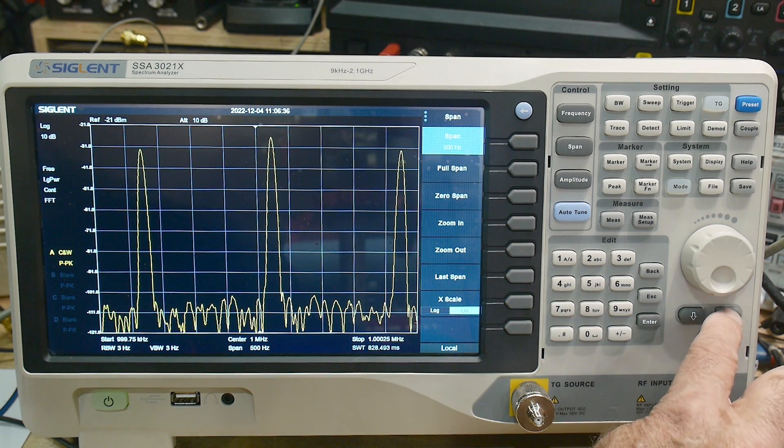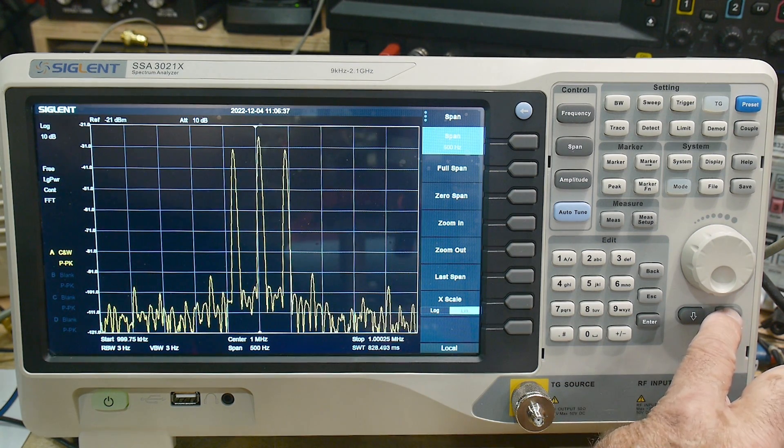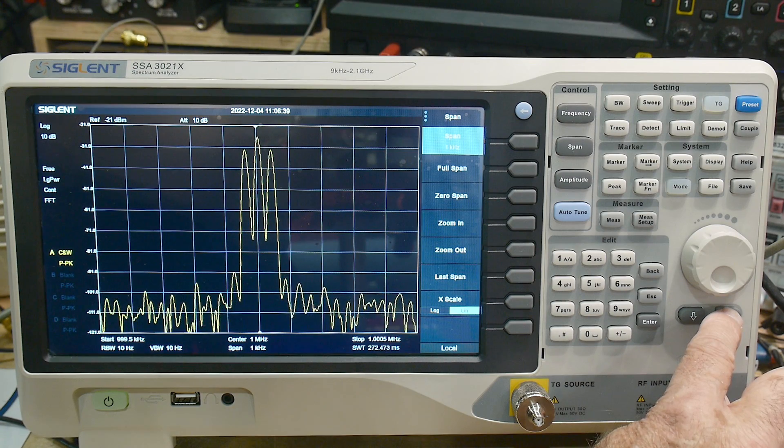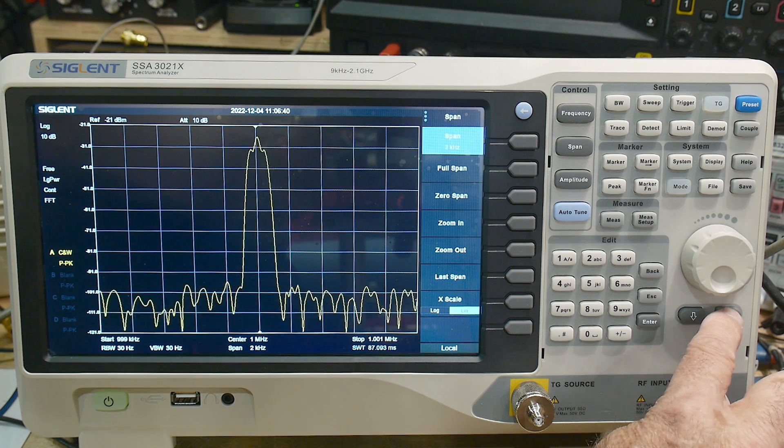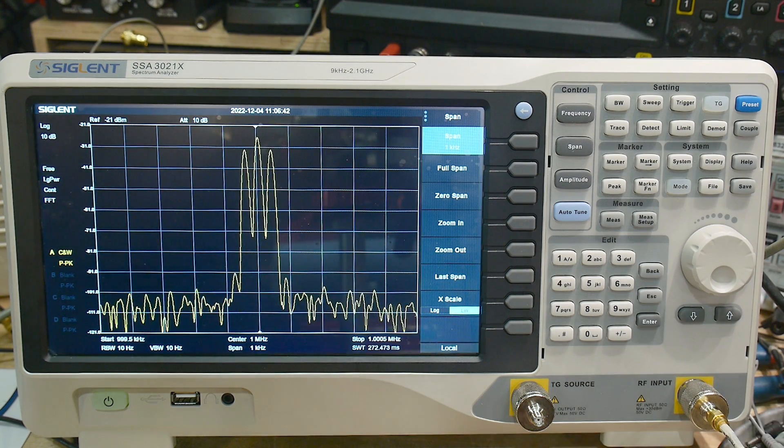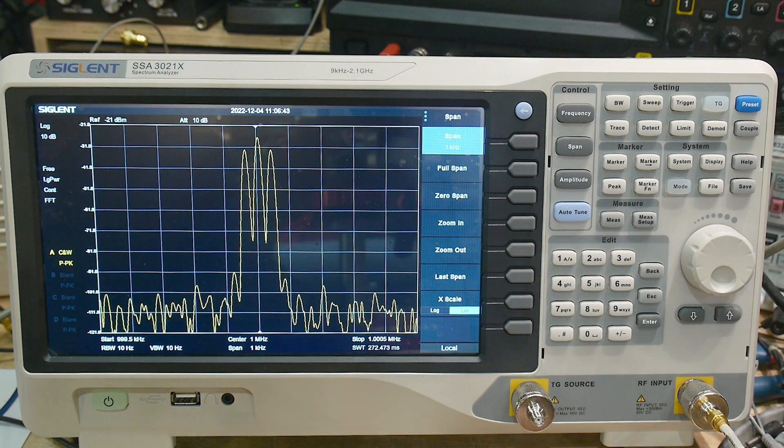1 hertz resolution is going to be about a 2.5 second sweep time. So that's pretty speedy for a 1 hertz resolution bandwidth. That's pretty crazy. Let's go ahead and speed it up again. So I'm very impressed with the instrument.